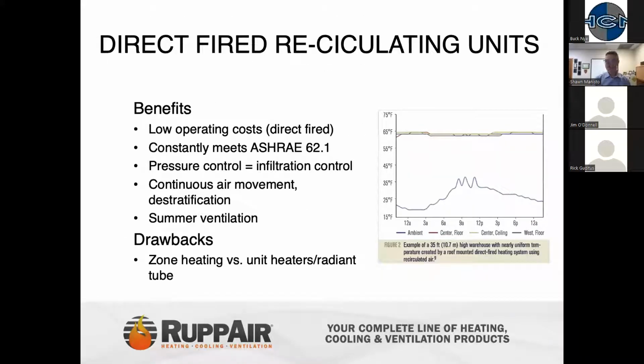So the big benefit on the recirc style systems is the lowest operating cost overall for the direct fire units. We talked about the 5 different systems. We talked about the unit heaters. We talked about air rotation. We talked about the radiant tube heat. Next, we talked about the 100%, and now we're talking about the recircs. So again, all of them have their place, but this is where we see the biggest bang for the buck. So that consistently meeting those ASHRAE standards, meaning the pressure control.